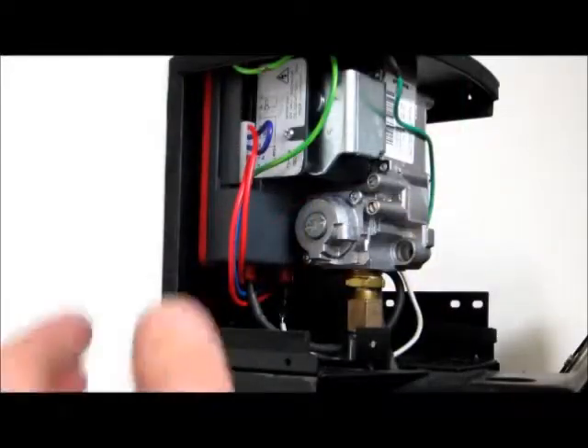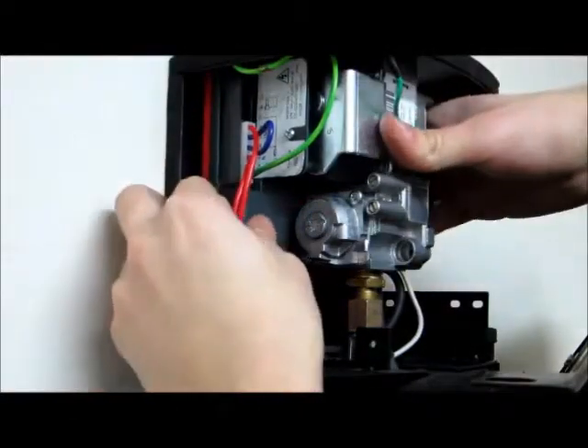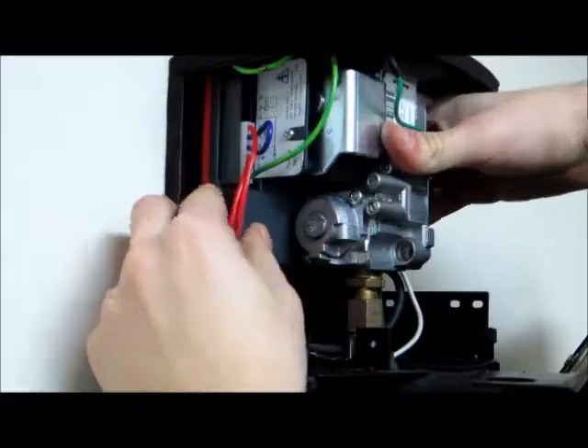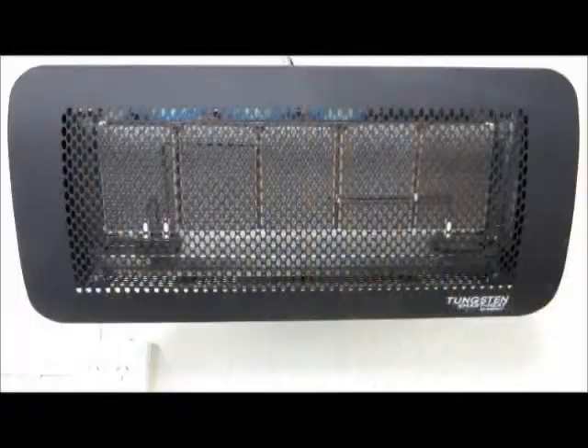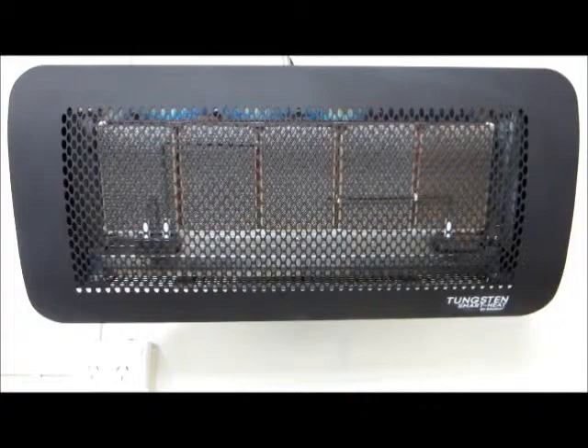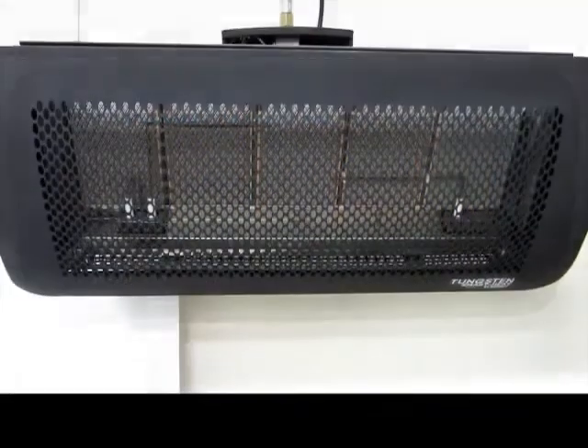If no damage is detected, ensure that the control box is correctly seated against the mounting plug located on the gas valve. When powered up, the unit should begin sparking between the ignition probe and the earthing rod. If a spark can be heard and not seen, the following steps should be followed. Turn the power to the unit off.